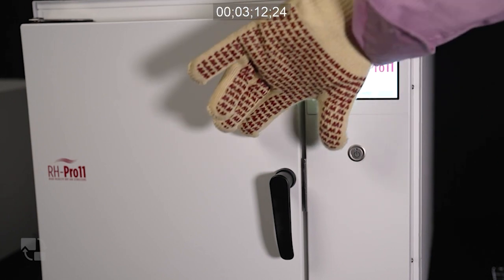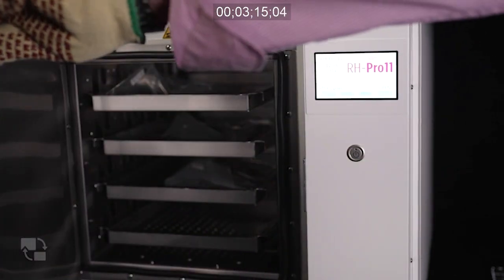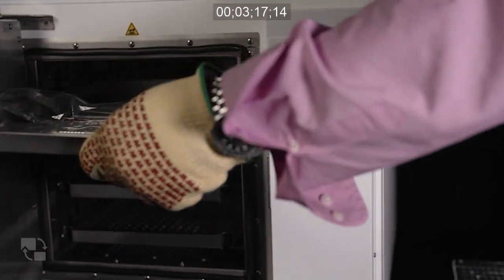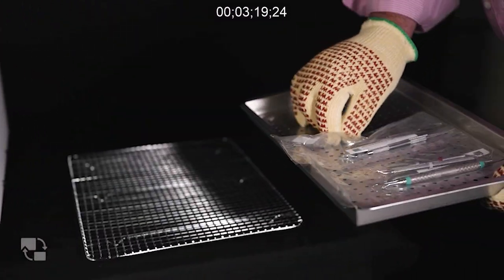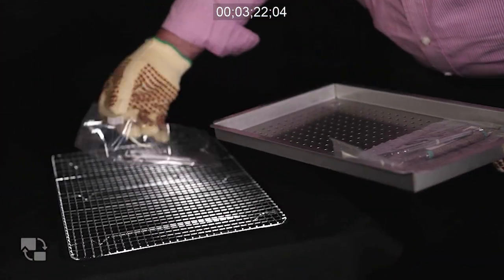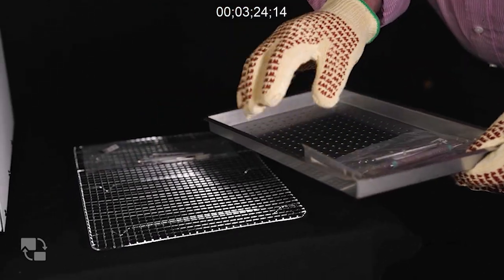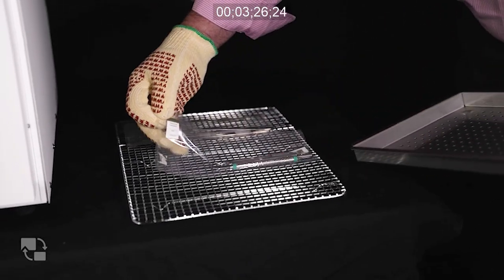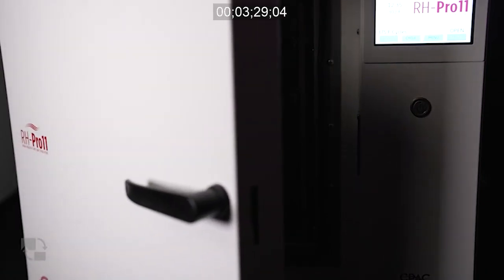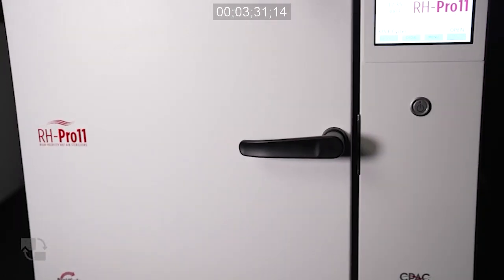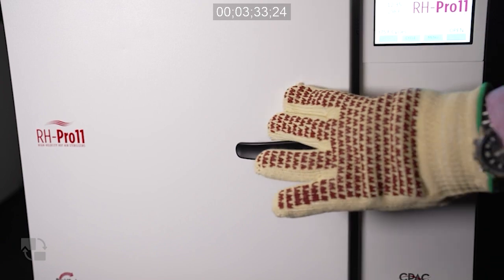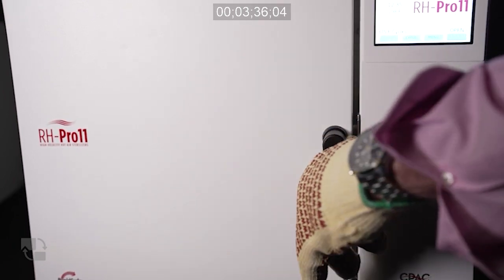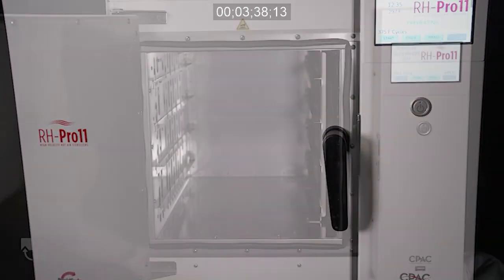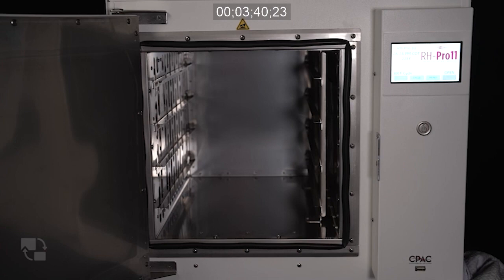When removing trays after the completion of a sterilization cycle, always use the heat protective gloves provided with the sterilizer or other oven-safe mitts. Place the trays on a heat-resistant counter surface or, for faster cooling, on a wire mesh rack. For continued use of the sterilizer, always close the chamber door after removing sterilizer loads so that the sterilizer can maintain temperature for another cycle. Leaving the sterilizer chamber door open turns the sterilizer off by automatically shutting down the sterilizer heating system.